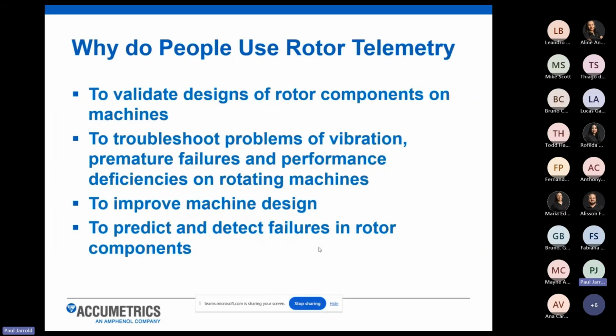So why would customers want to use telemetry? I mentioned some in the previous slide about getting away from things like slip rings or optical-based communication sensors or some type of other mechanical device used to contact a rotating shaft. All of our stuff is wireless. A lot of customers use it to troubleshoot things like premature vibrations, failures, and just overall performance issues on their rotating equipment. It helps them provide better machine design, but also can help them predict failures on their rotor components. So in this discussion, those failures we're going to be talking about primarily are going to be ground faults, and we're going to get into that next on what that means.